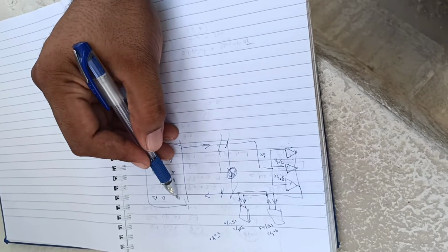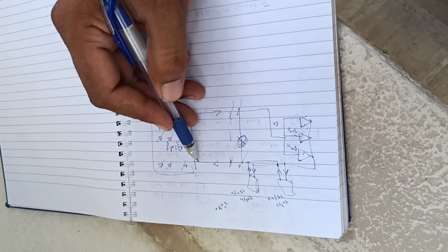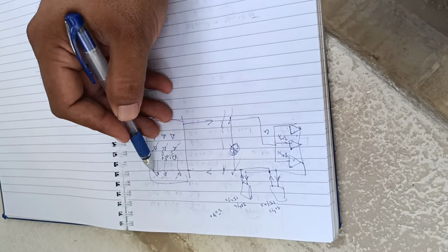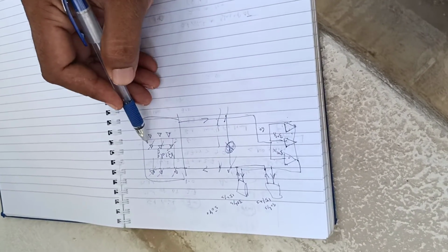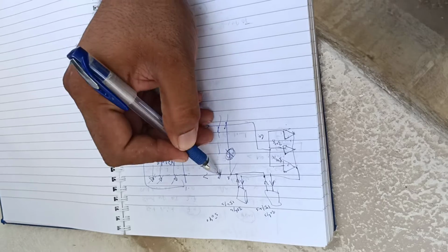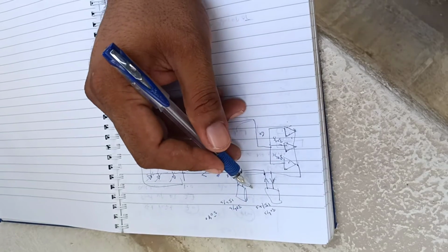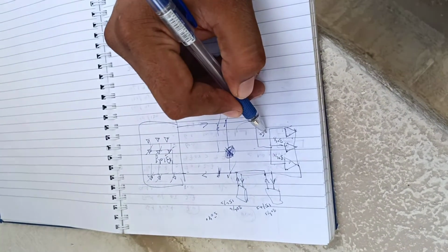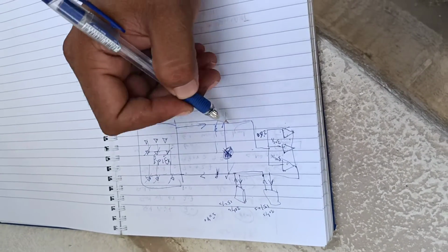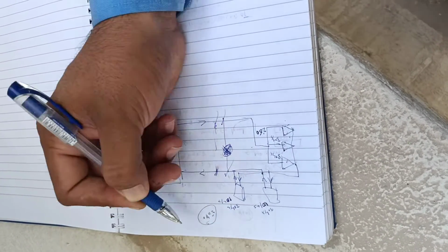Now what happens is that once your building reaches the temperature, it will start switching off the FCU valves. So your chilled water going to these FCUs will not come back, right? Yes, it will stick there itself. So now your return flow is reduced. Now in auto mode, once your return flow is reduced, the DP sensor senses the pressure difference and opens this bypass valve to maintain the minimum flow to the chiller. For example, now your return flow is 20 liter per second, because this bypass valve is off. Now what will happen here? Each chiller will be having 10 liter per second, which is less than 50% of our requirement.